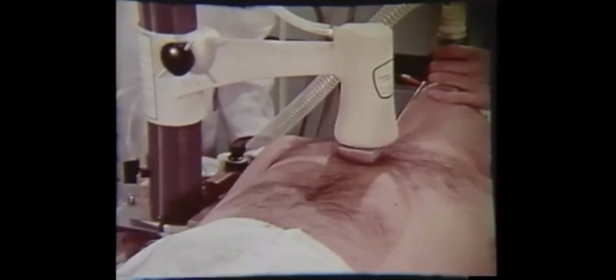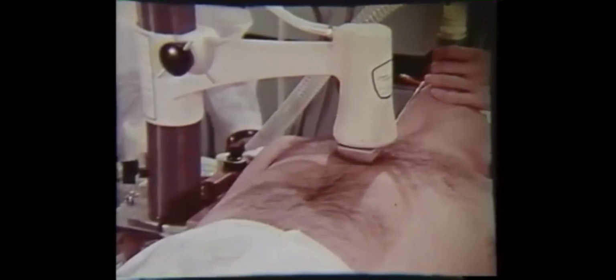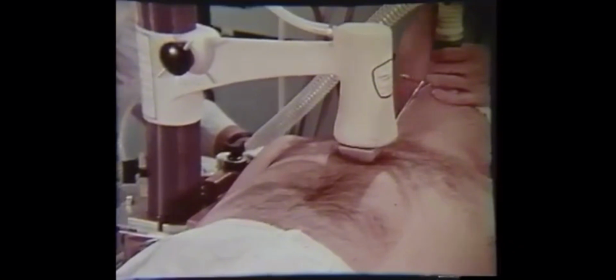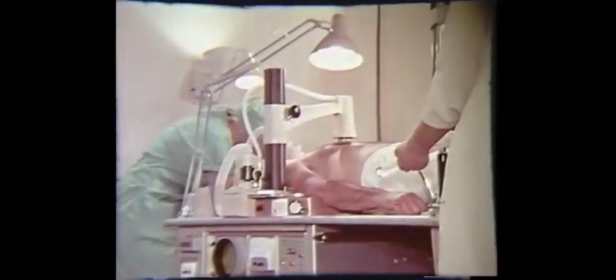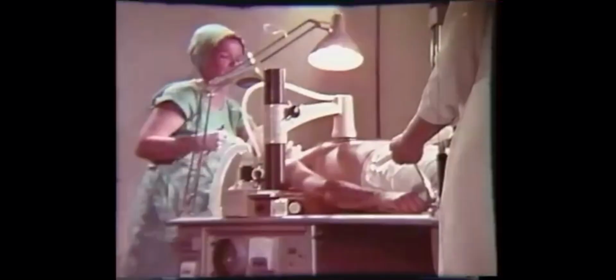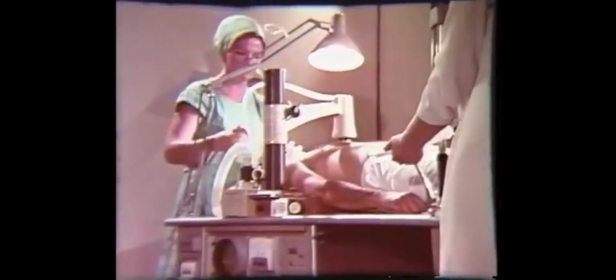After establishing basic support of the patient, plug in the AC power cable to conserve batteries for independent operation. If hospital electrical service fails, MAX automatically switches to its own power. When service is restored, all circuits automatically revert to hospital power. If defibrillation is required, confirm the diagnosis and turn on the defibrillator. The maximum 400-watt second power setting is usually employed for ventricular fibrillation.